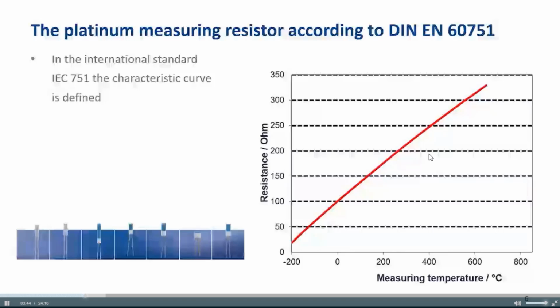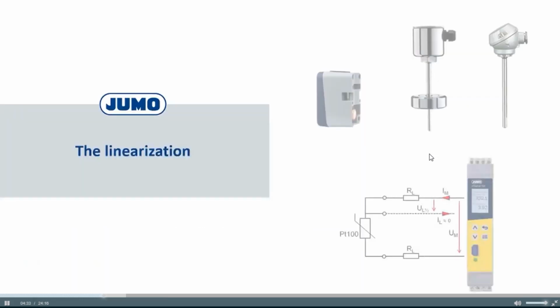The platinum sensors, PT100, PT1000, are standardized. There are a few things standardized there, but I want to say the most important thing is that the characteristic curve is defined. This means if you have a PT100 from one supplier, you can buy it from another supplier. You always buy a PT100, and the signal has the same behavior. This is very good. So if you buy a new device, you have no problems with the replacement. Sometimes if you work with NTCs, it's not so easy because each manufacturer has its own characteristic. Very important point.